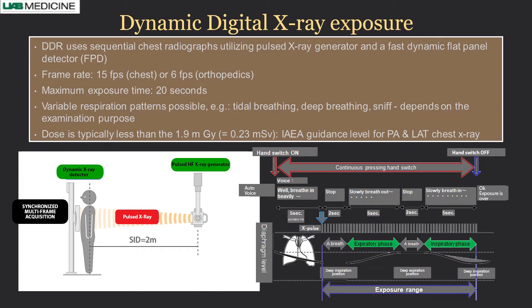Briefly, what it is: it uses sequential pulsed X-ray production from the machine. The X-ray travels through the patient at a distance of two meters from source to plate, and then a flat panel detector takes the images and processes them. When the hand switch is on during patient acquisition, you keep pressing the hand switch for 20 seconds for a complete 20-second exposure, then release the hand switch at the end.